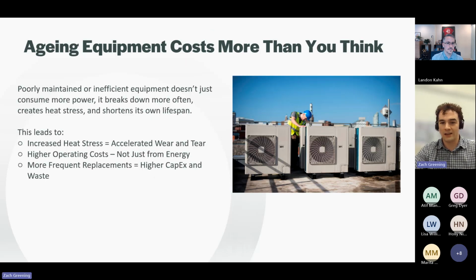Poorly maintained or outdated equipment isn't just an energy drain, it has cascading operational impacts that affect your bottom line, your workforce, and your environmental performance. Older motors, pumps, and lighting systems will often run hotter, especially if operating at fixed speeds or in a perpetual state of overload. Heat is the number one enemy of electrical components, and Australia gets pretty hot. High operating temperatures degrade insulation, bearings, and electronic control boards, shortening component lifespan and significantly increasing replacement costs.